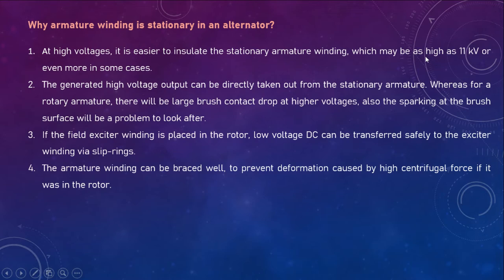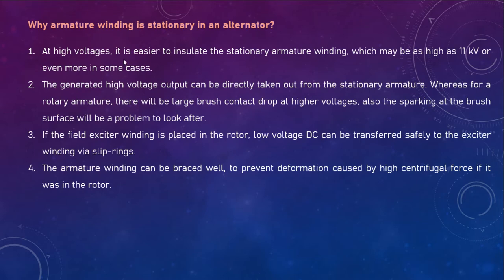The first advantage: at high voltages it is easier to insulate the stationary armature winding, which may be as high as 11 kilovolts or even more in some cases. Since it is a three-phase AC generator, very high voltage is given as output. If the armature were placed in the rotor, insulating the rotating armature would be very difficult. For that reason it is placed in the stator side, making installation easier.